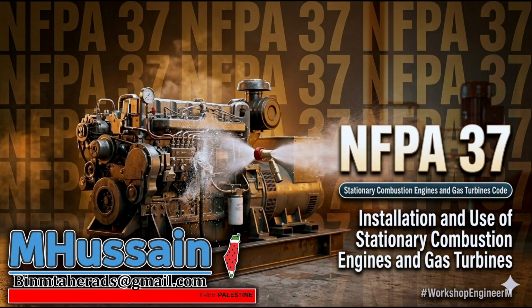But it gets worse. The manual fuel shutoff valve was located entirely inside the generator's weather enclosure. Think about that geometry. The generator's too close to a wood wall, and the valve to turn off the fuel is trapped inside the hazard zone. If a fire starts in there, the flames are threatening the wall, and no human is going to reach into a burning steel box to turn off a valve. The day tank will just continuously feed the fire until it's empty.